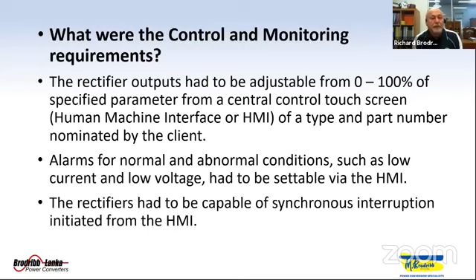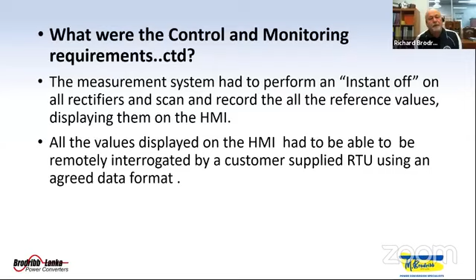It also had to be able to perform an instant off, a bit different to synchronous interruption, because in this case you switch the rectifier off and then rather quickly read the value of all the references. All the values displayed on the HMI also had to be remotely interrogated by a customer supplied RTU using an agreed data format. So not only was it available on the touchscreen, but whatever was on the touchscreen had to be echoed using a data format agreed on through the customer to their network.